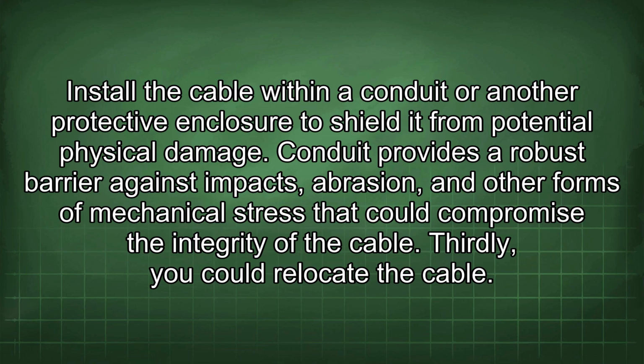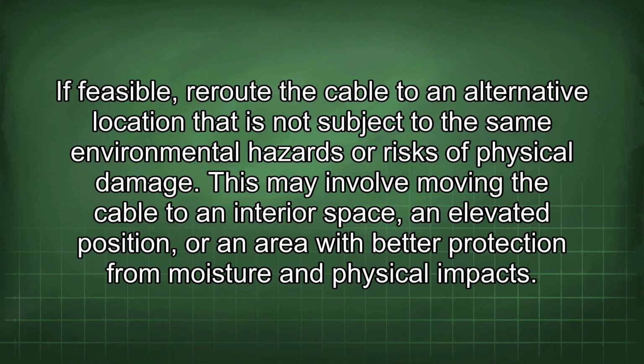Install the cable within a conduit or another protective enclosure to shield it from potential physical damage. Conduit provides a robust barrier against impacts, abrasion, and other forms of mechanical stress that could compromise the integrity of the cable. Thirdly, you could relocate the cable. If feasible, reroute the cable to an alternative location that is not subject to the same environmental hazards or risks of physical damage. This may involve moving the cable to an interior space, an elevated position, or an area with better protection from moisture and physical impacts.